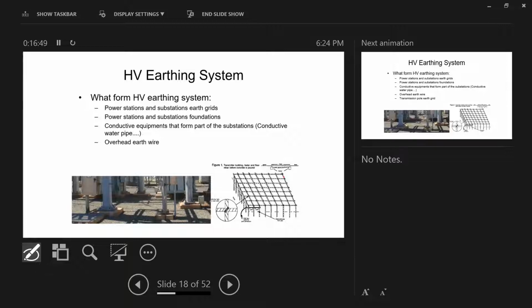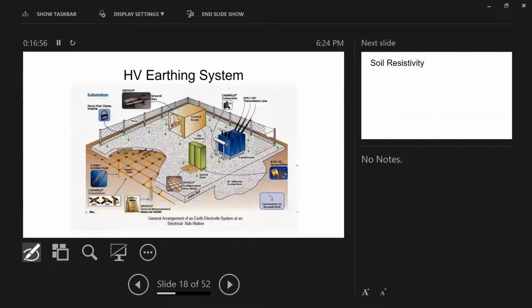Every single transmission line pole forms part of the earthing system because worldwide they have an overhead earth wire system. So for safety and operation purposes, we must make sure everything is bonded to the ground. Everything. If you walk inside a substation, you will see what is known as an earth mat. When you expect an operator to open and close the high voltage system, they always put an earth mat. This earth mat will be at the same potential to make sure that you are standing at the same potential. So even if this machine is at 1000 volt and your feet are at 990 volt, your voltage is 10 volt, which makes you safe.